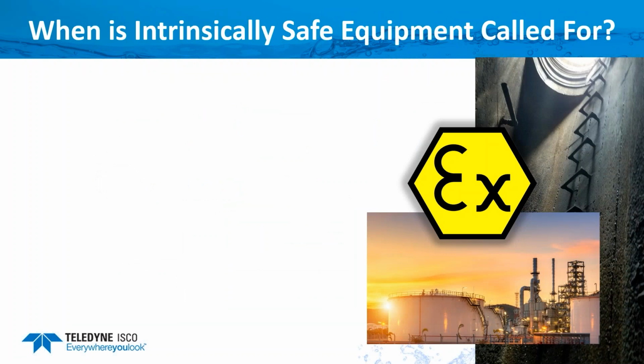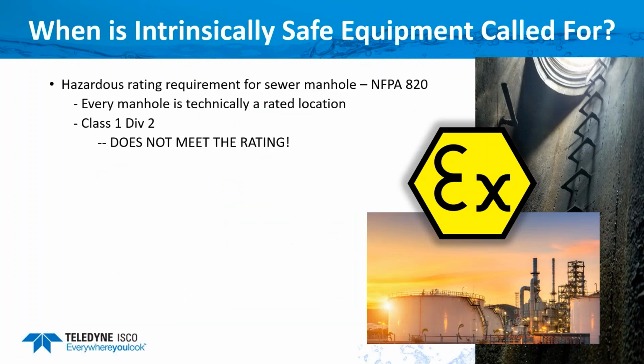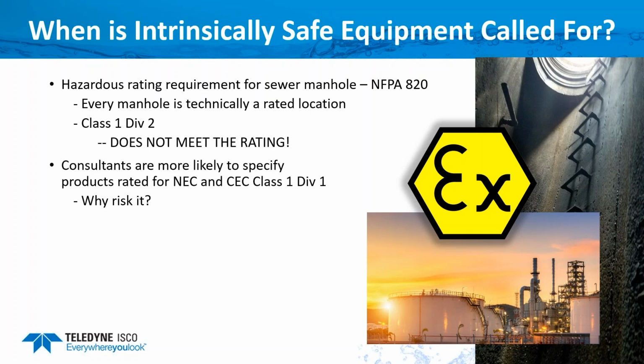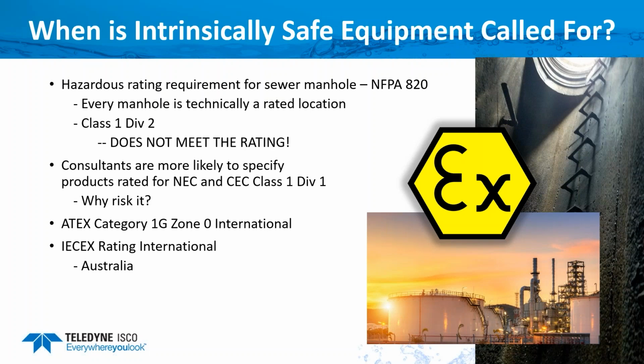So when is intrinsically safe equipment called for? Well, whenever a hazardous rating is required for a sewer manhole, known as the NFPA 820. Essentially, every manhole is technically a rated location. Now, Class 1 Div 2 does not quite meet that specification. You're going to find that consultants are more likely to specify products that are rated for NEC, CEC, Class 1 Div 1, ATEX applications. So why risk putting a non-classified sensor or flow meter in a location that has potentially hazardous gases? It may also be known as ATEX Category 1G, Zone 0 for international, or you may see it as the IECEx rating for the international in Australia.